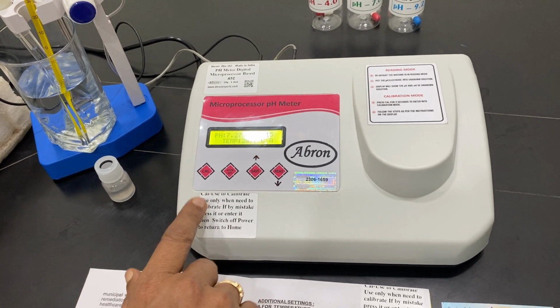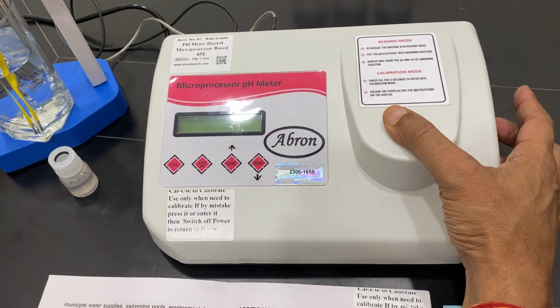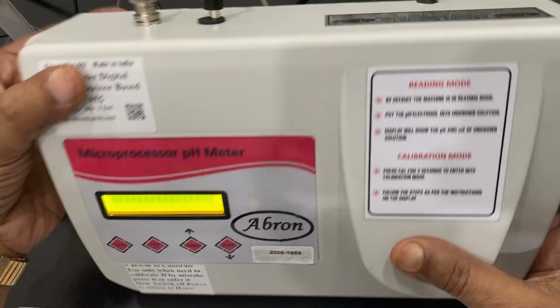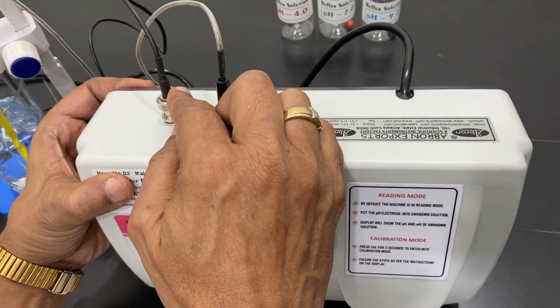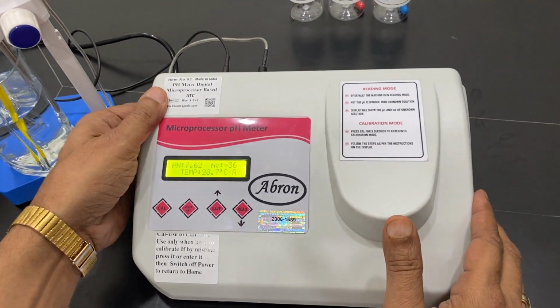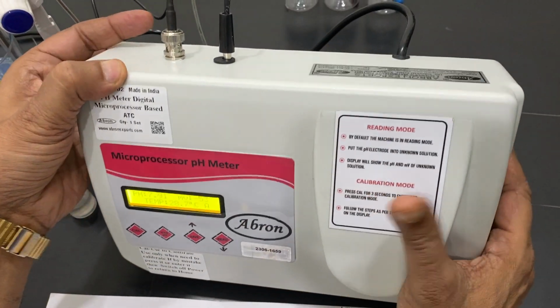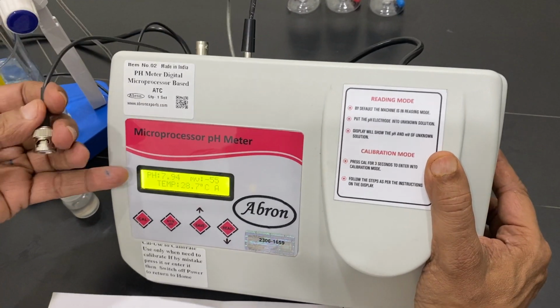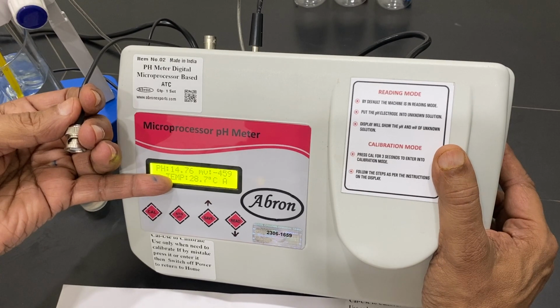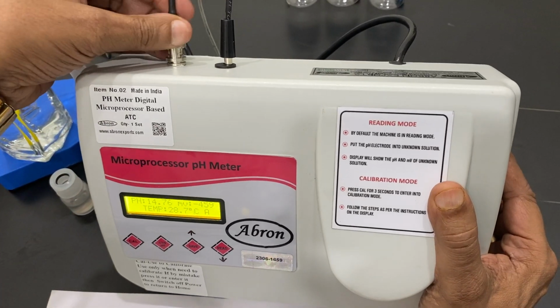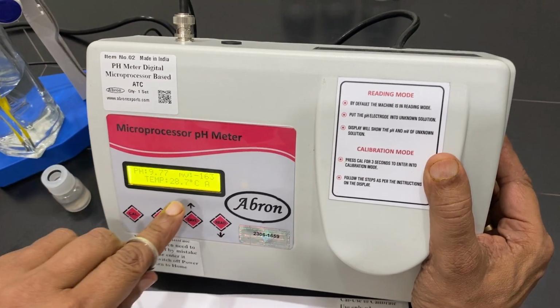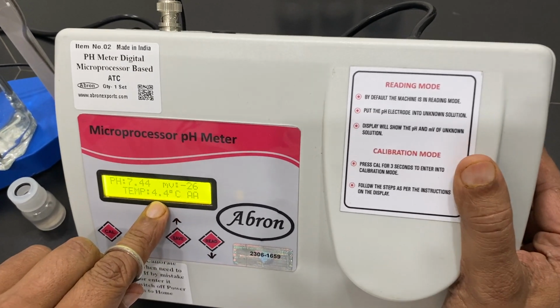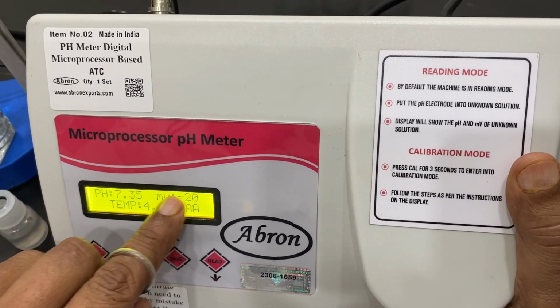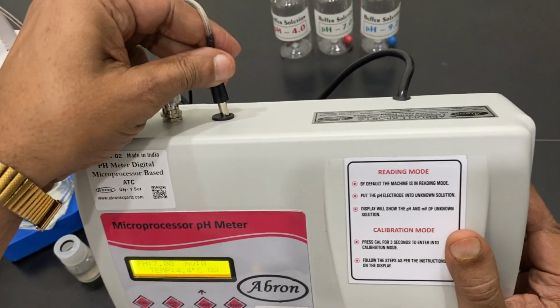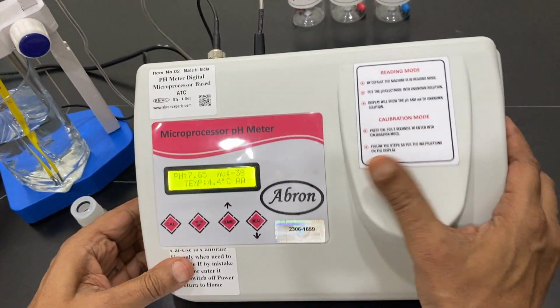The first is, when you switch it on, there are two electrodes. One is a thermometer probe, and the other is a combined electrode, and both must be attached. If either one is not attached, the readings may be wrong. And if the temperature probe is not attached, you can see the readings may be wrong. So obviously the temperature and these readings will change. So this probe should be attached.